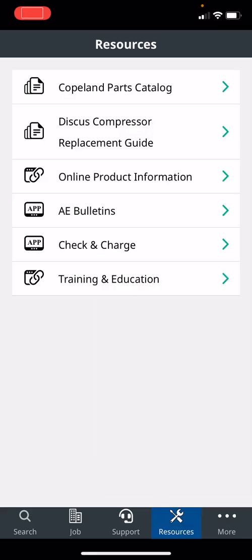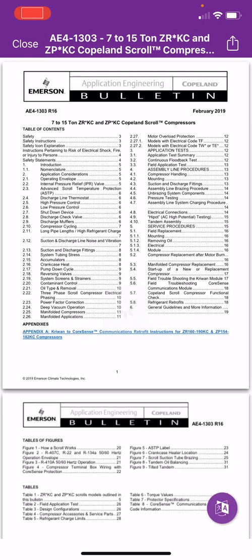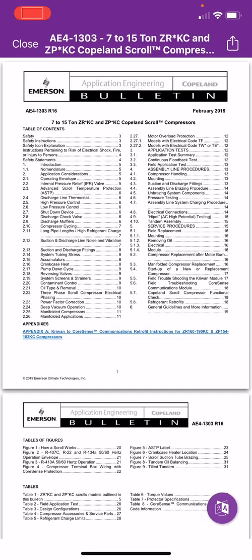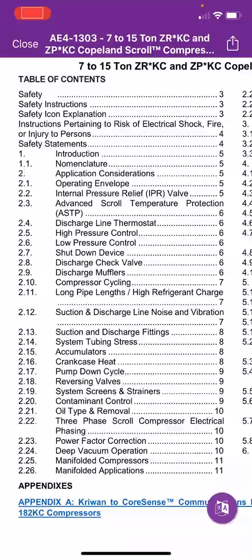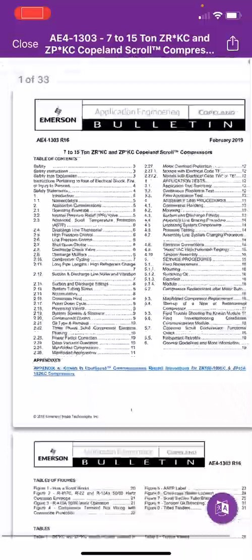The other ones, AE bulletins - if you don't have AE bulletins, this is the gospel for Copeland compressors. Any compressor that you work on that is a Copeland, here is the installation, maintenance, service manuals. I'll just pick on the very top one, 7 to 15 ton ZR compressor or ZP compressor. Right here, look: high pressure control, how do I set it, what do I set it for, discharge line thermostat, what is it, can I get one, what's the part number, low pressure control, discharge check valve, do I need one or not. All that information is in here.